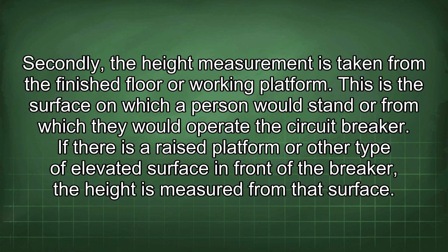If there is a raised platform or other type of elevated surface in front of the breaker, the height is measured from that surface. Thirdly, it is important to note that the 48-inch height limit is a maximum. There is no minimum height specified in the code, but practical considerations would dictate that the breaker should be installed at a reasonable height that is easily accessible to most people. In many cases, an electrician will install the breaker panel so that the majority of the breakers are within a comfortable reach range for both individuals with disabilities and those without.